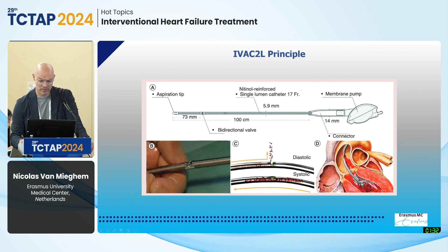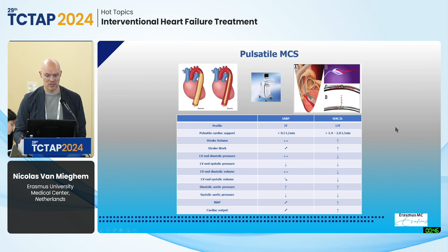As a matter of fact, it is an intra-aortic balloon pump on steroids. Where an intra-aortic balloon pump can generate approximately 0.5 to 0.6 liters per minute support, depending on the state of the heart and the patient, IVAC2L will give you 1.5 to 2 liters per minute pulsatile cardiogenic support. This will have immediate effects on stroke volume and stroke work that are more pronounced than balloon pumping, and you can also see immediate unloading of the ventricle with an IVAC2L that is hardly present with an intra-aortic balloon pump.